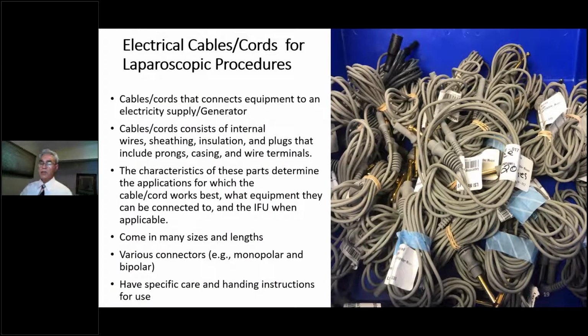On the electrical cords and cables, obviously most of the laparoscopic surgical instruments have either bipolar or monopolar cords. Looking at their IFUs, there's not really a consistent approach to how you sterilize them and how many times. We saw some rated for 10, 15, 20 times. Some didn't have numbers on them at all. And some, I guess, people assume they're good forever. We found out that that's not the case.